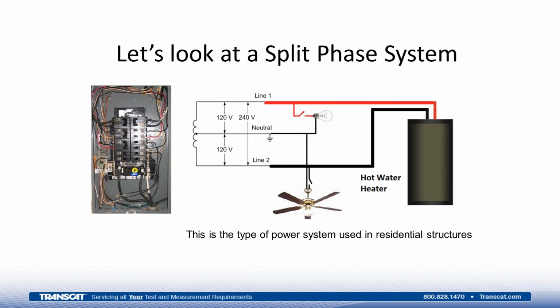You would put the single phase loads, things like fans and or lights, across either phase to the neutral by attaching the fan to L2 and the light to L1. I'm kind of balancing my load. If I could, and there's no reason I couldn't do this, I could put both the light and the fan on phase 2 or phase 1, but the result of it would be I could be loading one line more than the other, and it's beneficial to have the loads being balanced as much as possible.